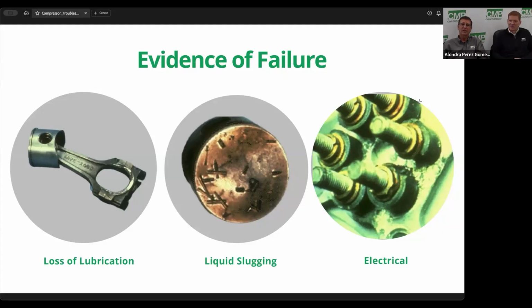The other one would be the gut feeling. In other words, when you're charging the system up and you close the valve on your gauges on your suction, and your suction pressure is either maybe 10 pounds lower than you thought it would be, or maybe 10 pounds higher than it should be, then that's your gut telling you there's something wrong with the system. So maybe you don't want to leave it there. Maybe you want to check a little further into why I am running a lower or a higher suction than I really should have. And that's what I call your gut feeling. Yeah. Oh, for sure. Go with your gut.